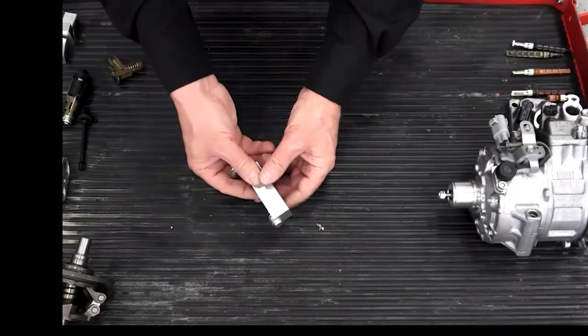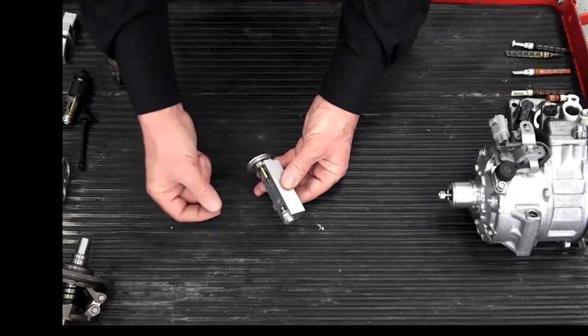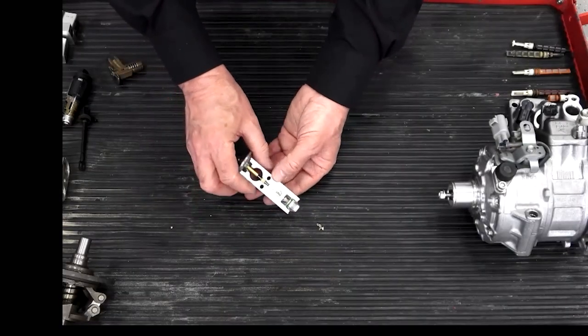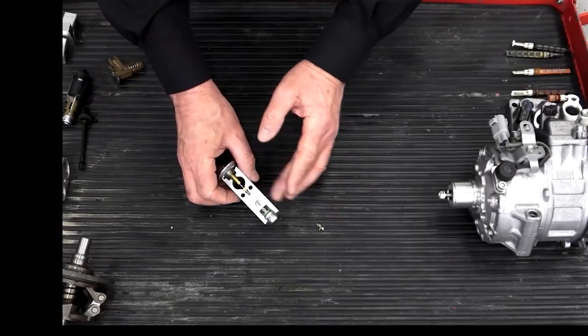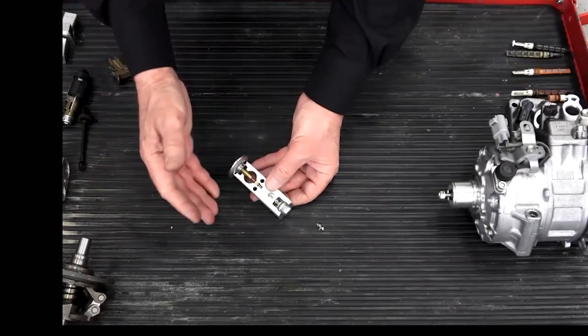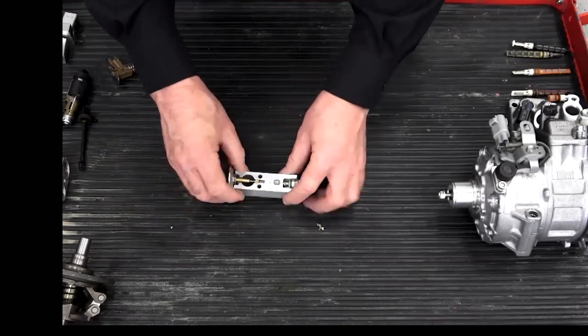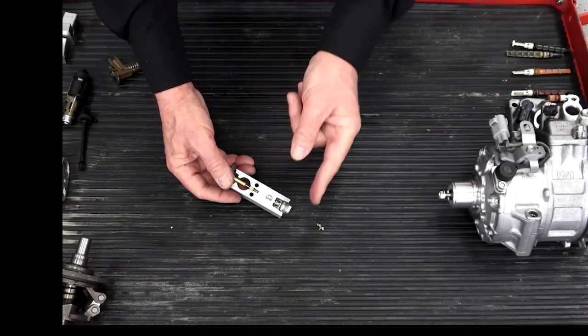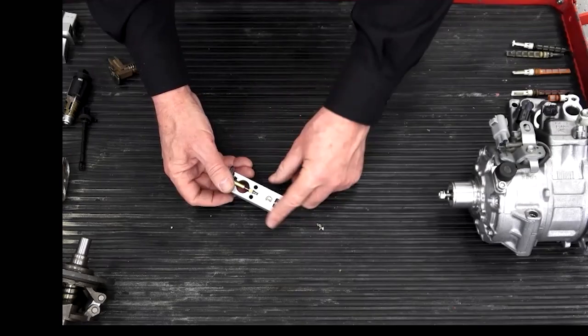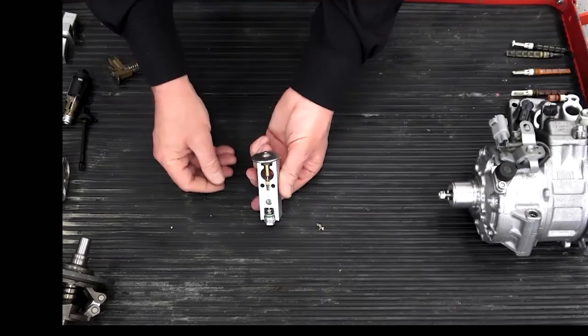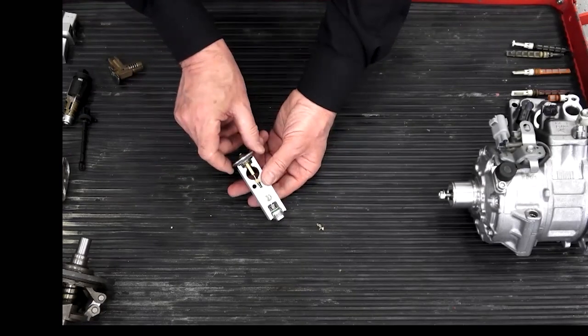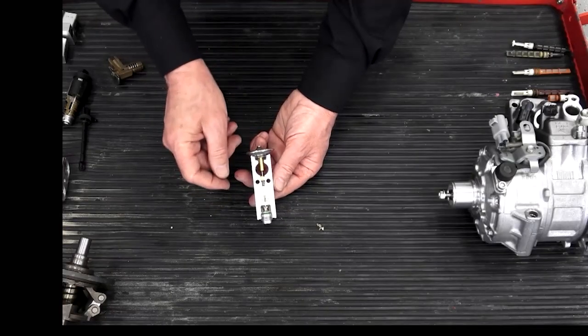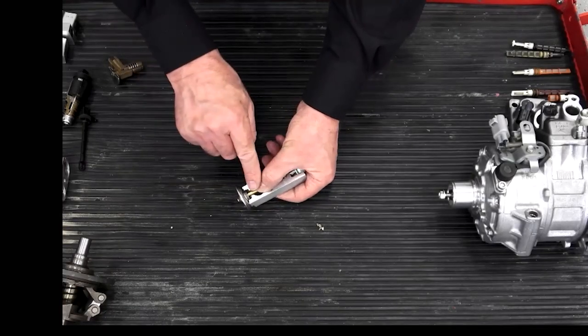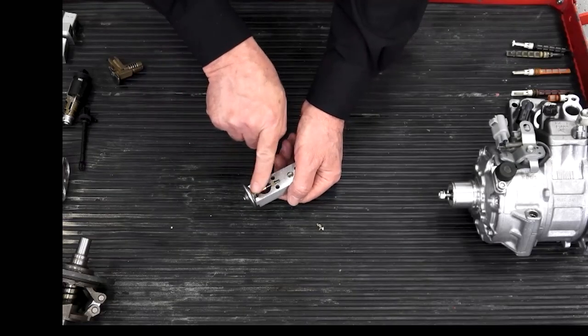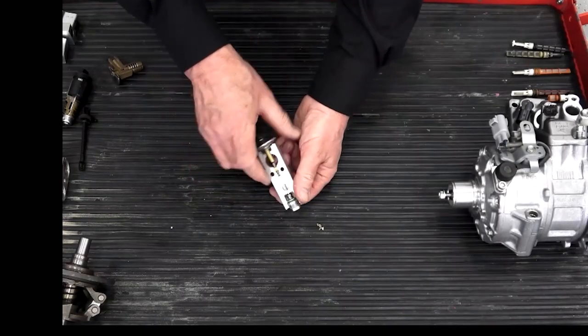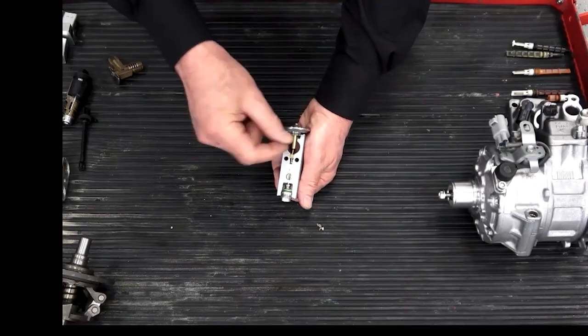In other words, how much refrigerant it will actually allow to flow. In other words, how much real estate it can cool, right? It will also have a specification for superheat. Most of them start maybe around 4 degrees all the way up to 14 degrees, give or take, for most automotive applications. And that superheat value is how much temperature increase it will allow across the evaporator to prevent liquid locking or slugging the compressor. And the third specification is MOP, or maximum operating pressure. That's the pressure acting in the evaporator, the pressure acting in the bottom of that diaphragm. It's the maximum pressure at which the TXV valve will allow refrigerant to flow.